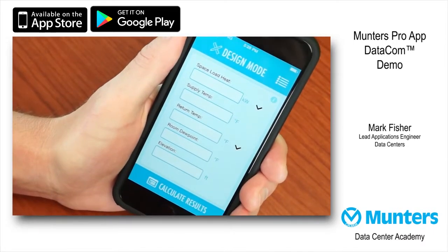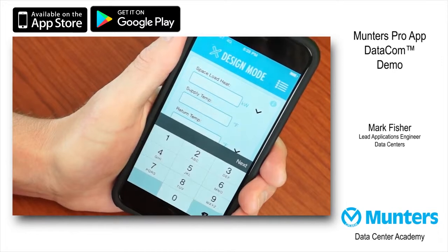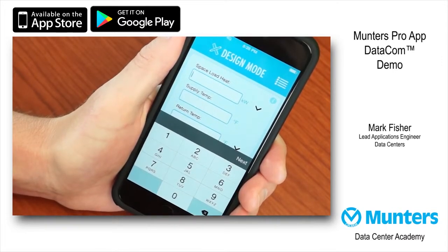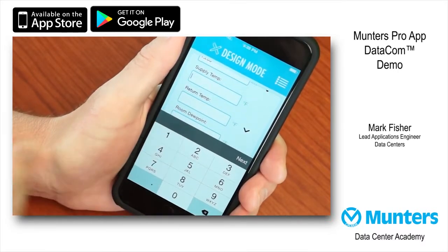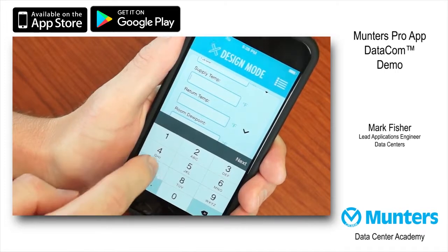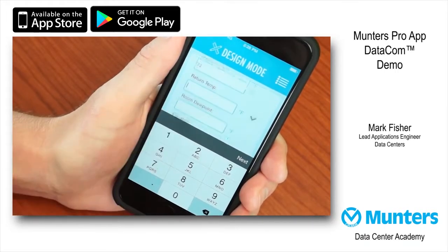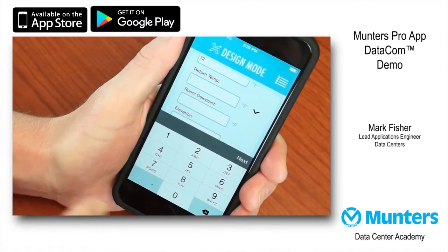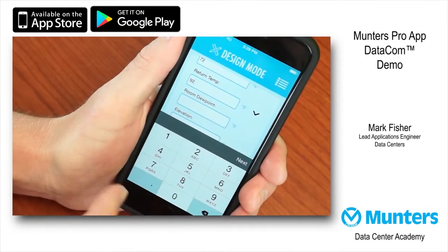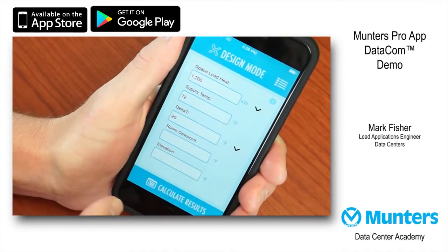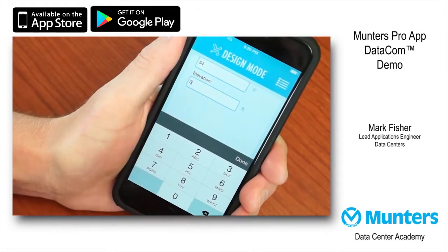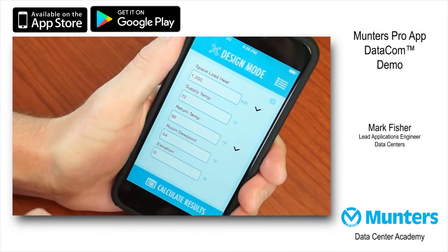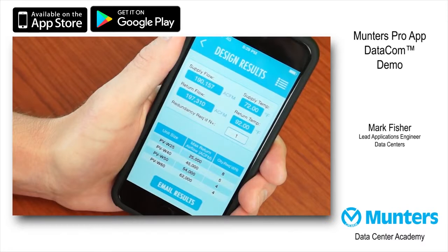There's several inputs on this screen, and I am going to simulate a hypothetical data center that is 1200 kilowatts, and we're going to be running a supply temperature of 72 degrees Fahrenheit. And I want to run a 20 degree delta T, so I can either plug in 92 for my return temp, or you can actually toggle between delta T if it's easier to put it in that way. I'm going to set the room dew point at 54, and I'm going to run it at sea level. Those are all the inputs I need, and now I'll be able to see the results by hitting the calculate button.